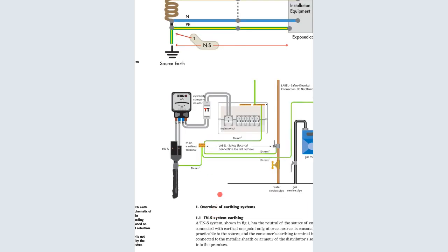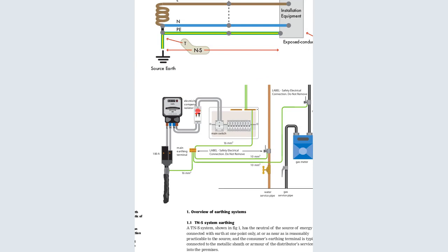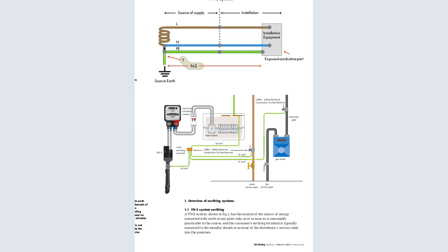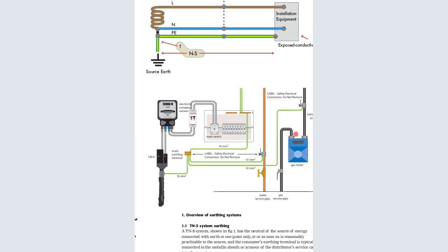So let us see. Let me zoom out this one so that you can see. So if this is the meter, the electrical company, that is like Kenya Power. This is the gas meter. This is the water pipes. I said all the metallic parts are normally bonded. The bonding means they are connected to the earth mass, meaning all of them have cables tapped and joined at one point. This is the main earthing terminal. It is here. You can see the meter box here is earthed, and all the earthing cables are joined at this point. And this 16mm cable is drawn to the electrode.